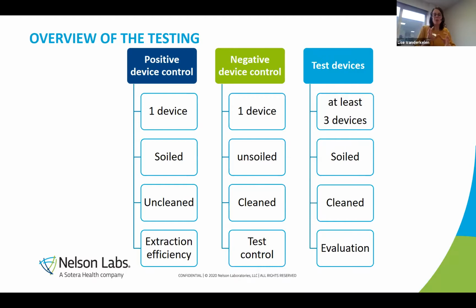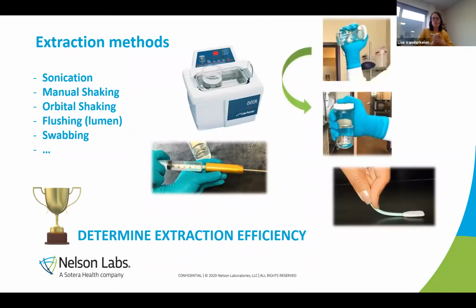And then we will take at least 3 test devices, which we will use for the evaluation of our cleaning procedure, which are soiled and cleaned. So that is very crucial, to take the controls into account. Without the controls, you cannot conclude anything. So how do we remove the soil traces from the device? By extraction. This can be sonication, swabbing, manual shaking, flushing.